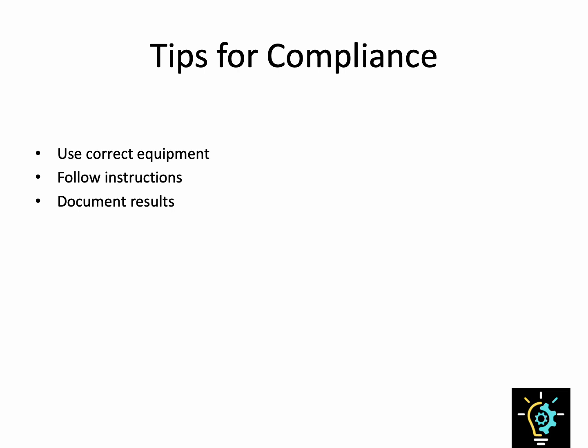If you're responsible for compliance, here are a few practical tips. First, always use testing equipment that's designed for IEC 62353. Many modern electrical safety analyzers have built-in routines for it. Second, don't skip the basics. Visual inspection most of the time reveals the issues before any electrical test does. And thirdly, remember that insulation resistance tests, while optional, can provide valuable insight. But only run them if the manufacturer confirms. So always check the service manual, making sure that it won't damage the device.